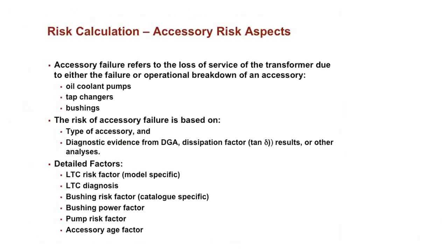Okay. And one thing I want to note: wind farms, there's a lot of wind farms going up in the last 5-10 years. They tend to have a higher dielectric failure rate. Right now the industry is starting to understand that, and the standards are going to be changed for that. My opinion is that wind farms are seeing a lot more transients and harmonics than the transformers were designed for. They almost need to be designed more as an industrial transformer than a regular power transformer. But we take that into account when we're looking at risk factors.